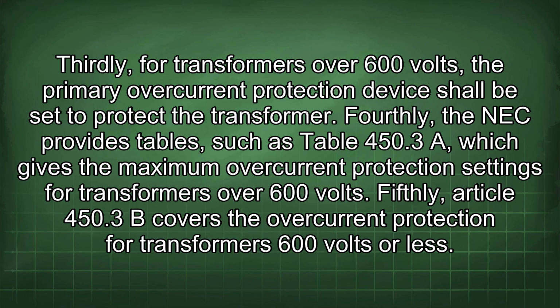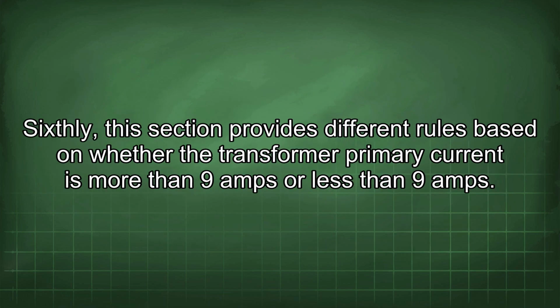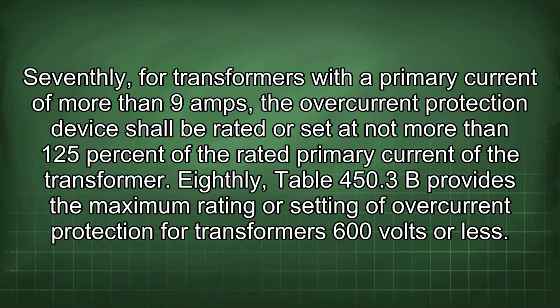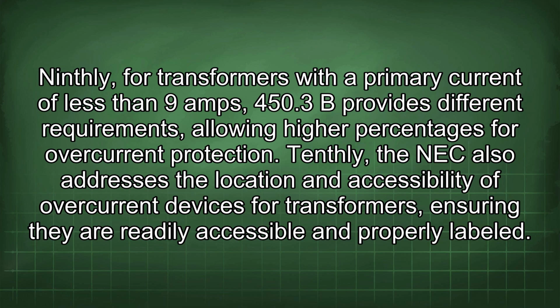Fifthly, Article 450.3(B) covers the overcurrent protection for transformers 600 volts or less. Sixthly, this section provides different rules based on whether the transformer primary current is more than 9 amps or less than 9 amps. Seventhly, for transformers with a primary current of more than 9 amps, the overcurrent protection device shall be rated or set at not more than 125% of the rated primary current of the transformer. Eighthly, Table 450.3(B) provides the maximum rating or setting of overcurrent protection for transformers 600 volts or less. Ninthly, for transformers with a primary current of less than 9 amps, 450.3(B) provides different requirements, allowing higher percentages for overcurrent protection.